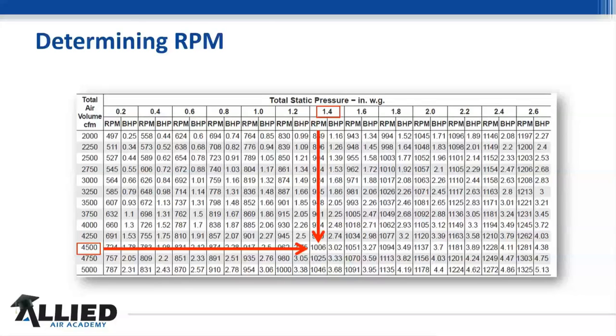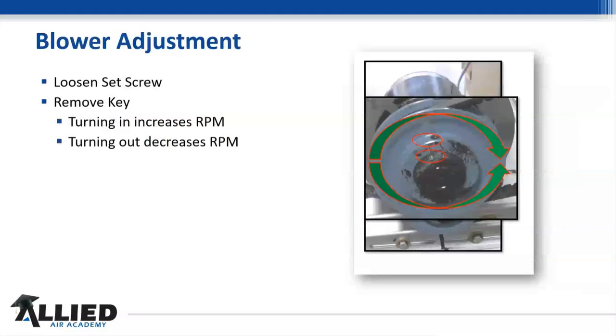So then we got to make our adjustment on the pulley. On this, you do have to loosen the set screw and remove the key. And I put this on here, and when I do these classes, I kind of jokingly say you have to remove the key, because I had a phone call where a guy didn't, and it wasn't funny, but it was funny to hear him grunting trying to turn that with the key still in there. So you want to turn it in to increase RPM and turn it out to decrease RPM.